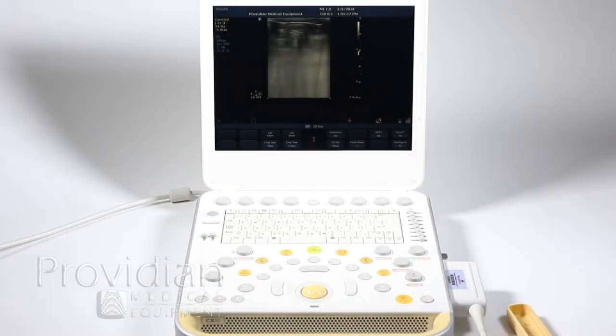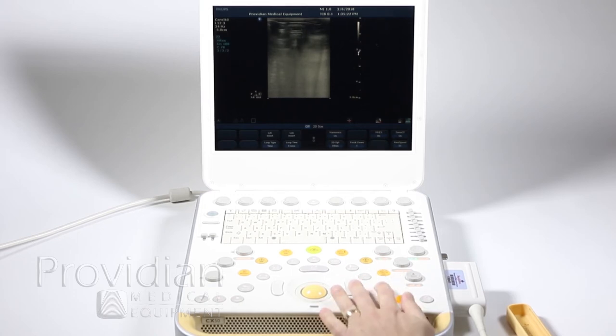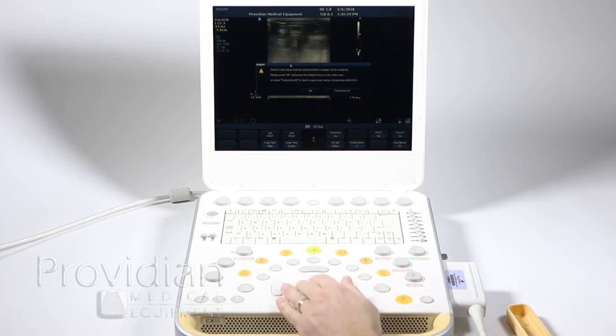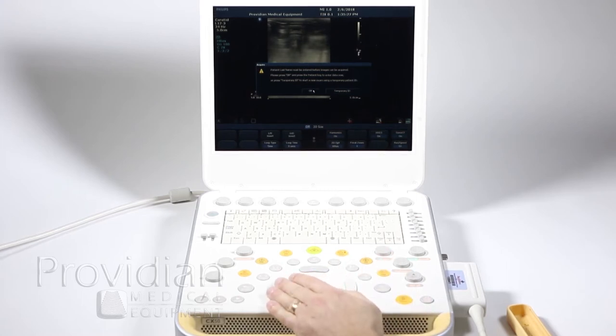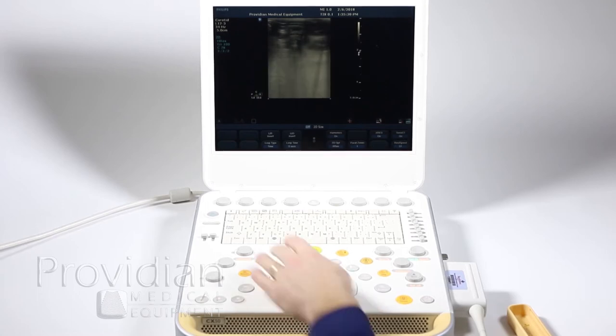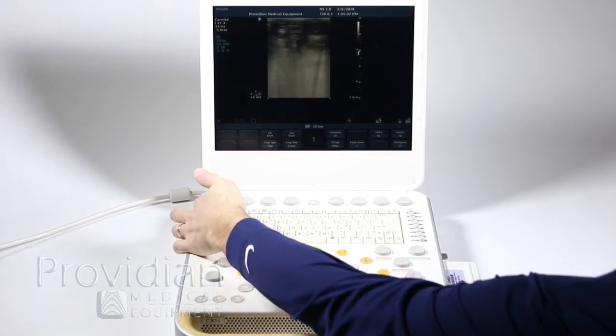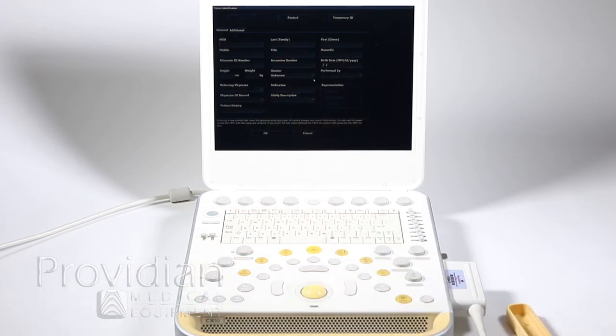Although this starts up on boot to an imaging screen and you can scan, you're not going to be able to save any images. It will tell you that you have to have a patient last name and an MRN number before you can do anything. So just go ahead and click OK, and we'll go up to this patient key here and enter the patient.